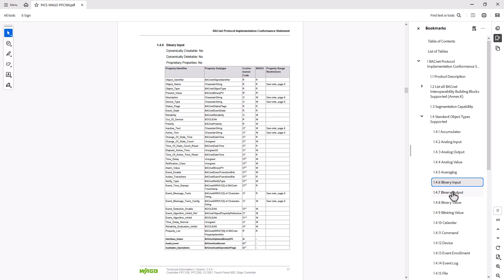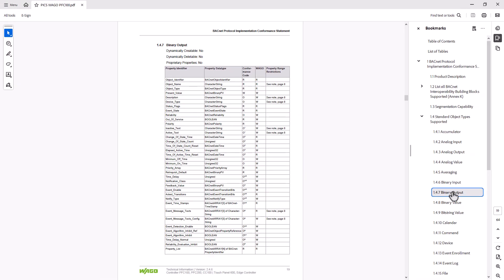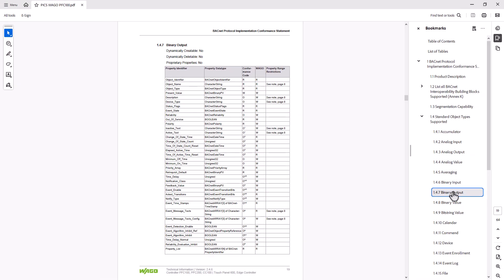In the binary output object, however, the present value can also be written. All objects and properties listed in the PICS can be processed by our BACnet controller. It also follows that objects or properties not listed here cannot be used by this controller in client mapping at this time.